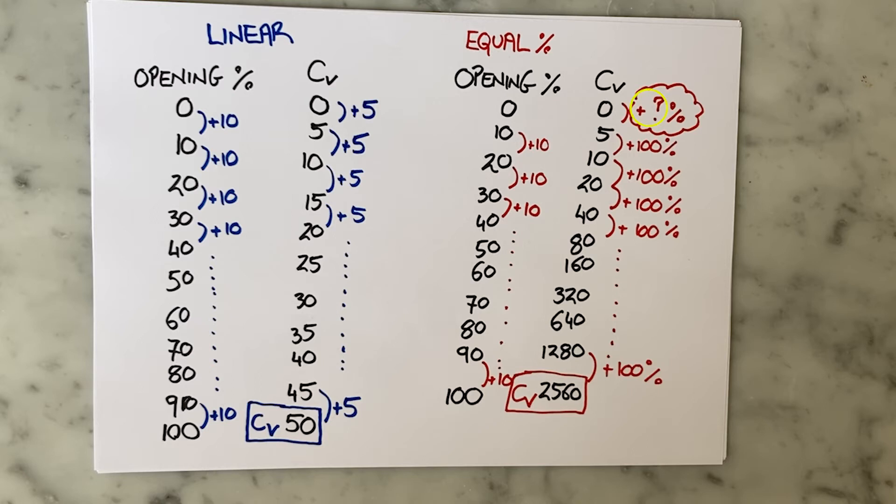So you first need to know how much does the CV increase upon initial opening of the valve, and secondly you need to know once it is open what is the percentage increase in flow for a given step change in valve opening.